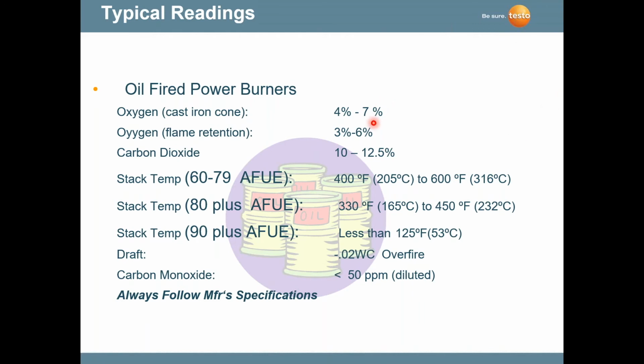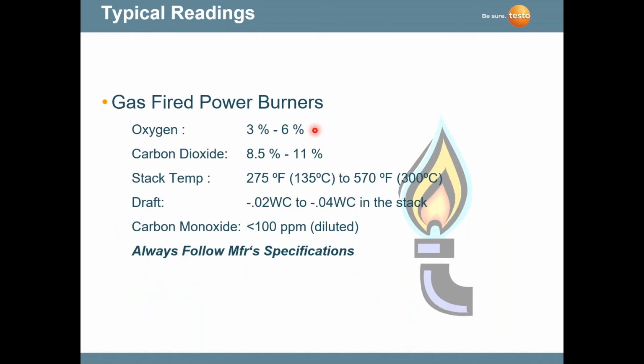So you see here the oxygen readings on cast iron cone, flame retention, carbon dioxide reading, the temperature readings in degrees C here, draft overfire. And then here's your carbon monoxide reading, which is less than 50 parts per million. So gas-fired power burners, 3 to 6% on oxygen, carbon dioxide readings, stack temperature readings between 135 and 300 C. Inches of water column, draft, less than 100 ppm CO on the carbon monoxide.